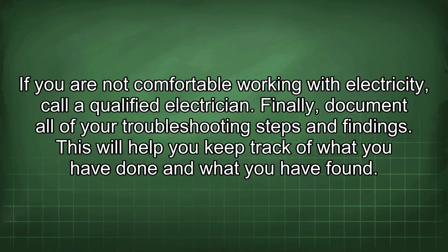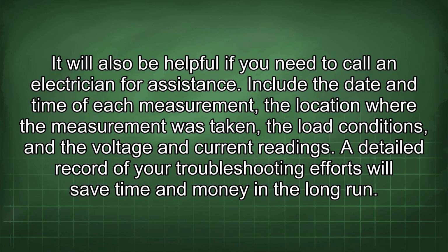Finally, document all of your troubleshooting steps and findings. This will help you keep track of what you have done and what you have found. It will also be helpful if you need to call an electrician for assistance. Include the date and time of each measurement, the location where the measurement was taken, the load conditions, and the voltage and current readings. A detailed record of your troubleshooting efforts will save time and money in the long run.